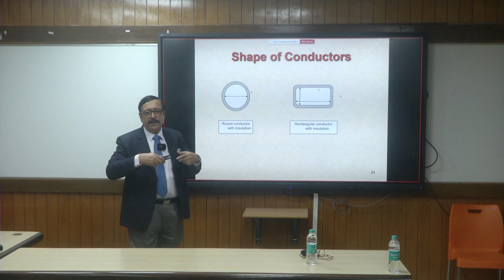You have different types of losses in the conductor, particularly at high frequency, also at lower frequencies. First of all, you have the skin effect. Because of the skin effect, most of the current tries to concentrate on the periphery of the conductor, and so effective utilization of the conductor is not there. So when you talk in terms of current density, the amount of current per square millimeter, the actual current density in this part is much higher, so your effective resistance of the conductor is much higher than the DC resistance, and that we call the AC resistance, because most of the current is flowing through only a part of the skin. So you have higher AC resistance. So the solution is, you don't go in for very large diameters, because the AC resistance depends on diameter, we'll see.